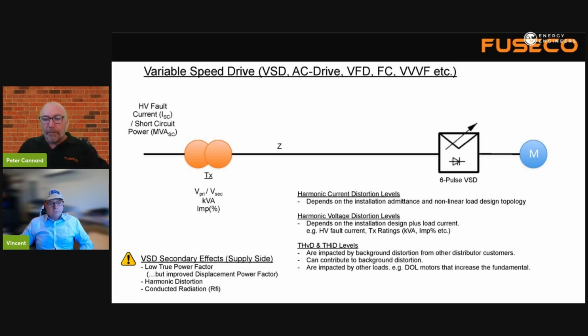So power factor itself, we've determined, depends on the motor and the makeup of the motor, which is to do with how many poles there are in that motor, which is to do with how many inductors essentially inside the motor. The variable speed drive has internal components that can impact how much harmonic content you will have on the supply, or how bad the lumps and bumps or the camel humps are.